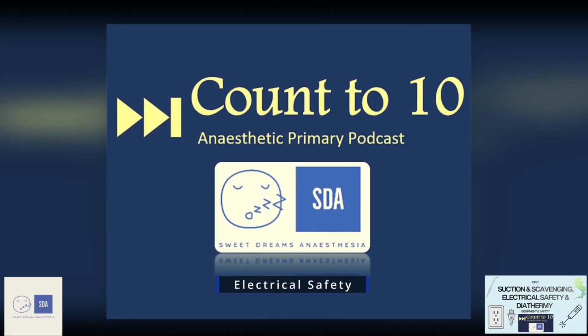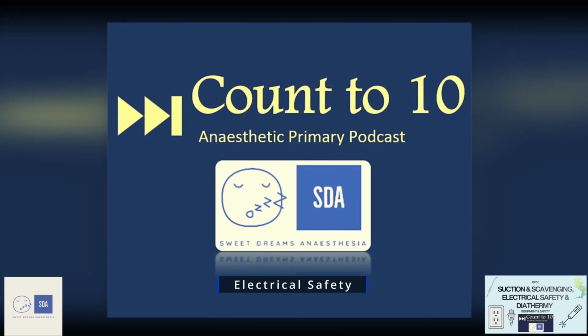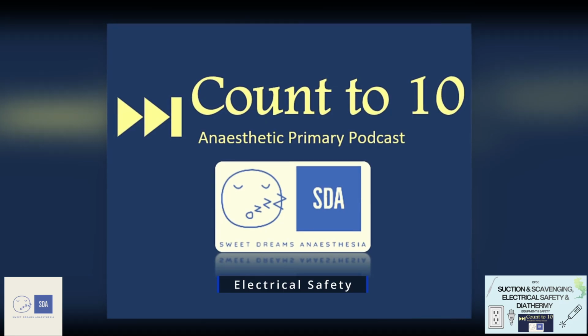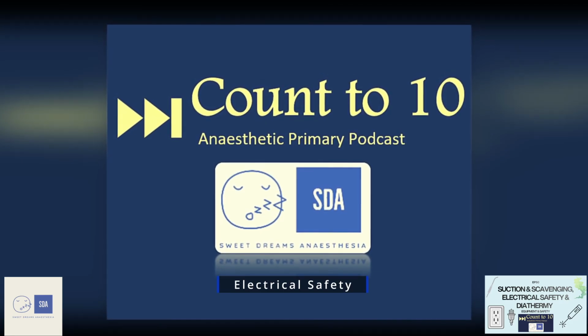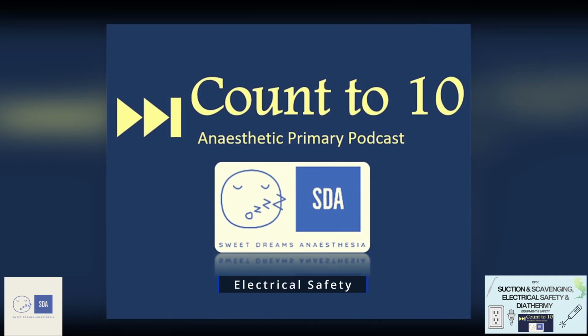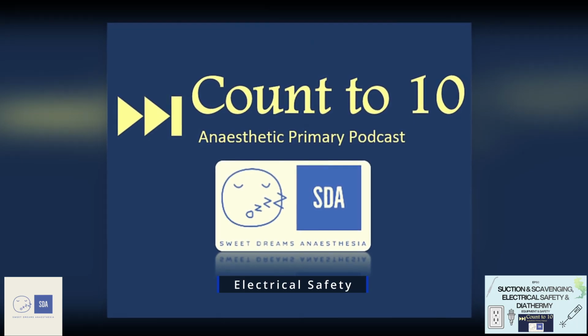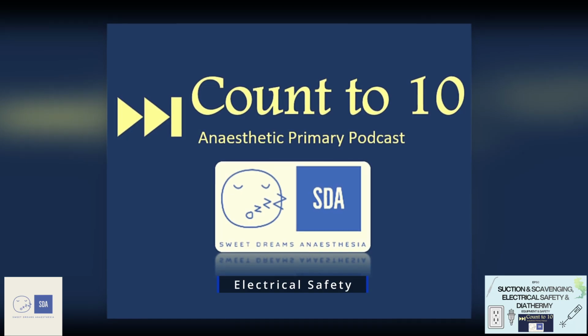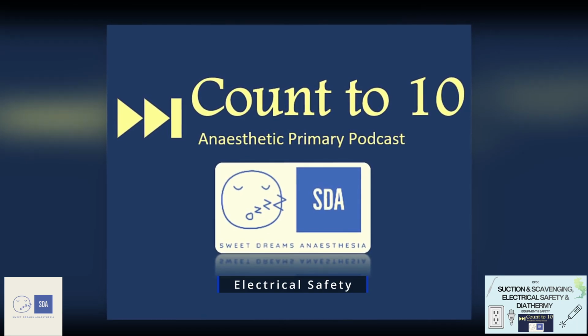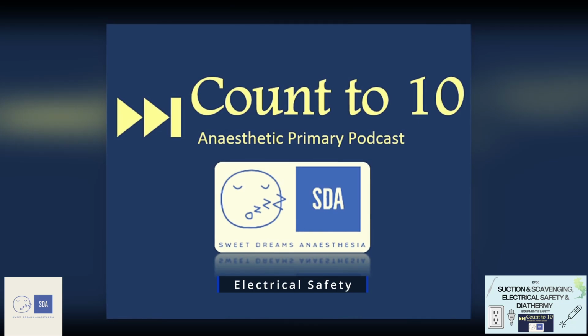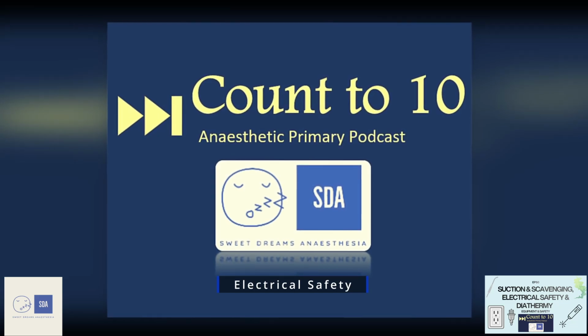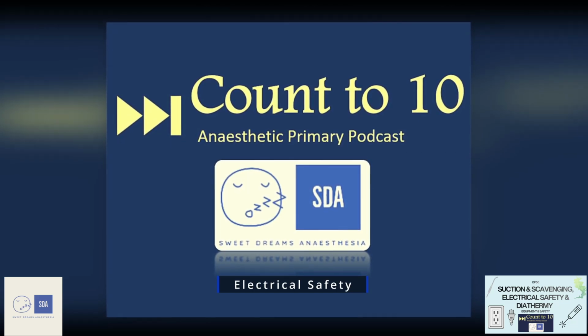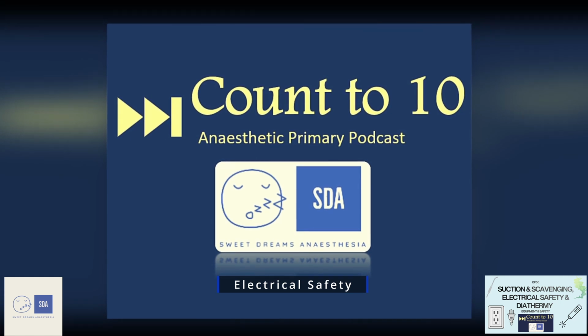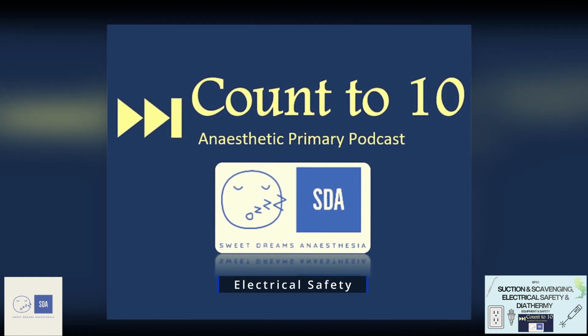Then there's a third and final layer of protection against electrocution, which is very unique to critical areas such as the operating theatre. And this is the equipotential earthing system, or the EES. The simplest way to think about this is that you use large diameter copper cables to combine all the earth points into one earth point, because each different earth point may have its own different potential difference. So by combining them all into one, it equalizes all the potentials of all the earth points.